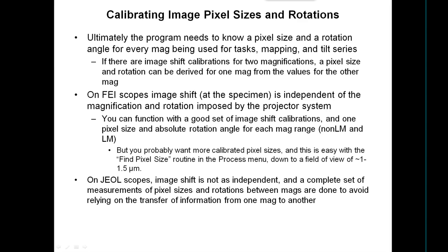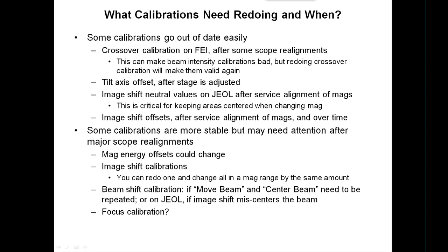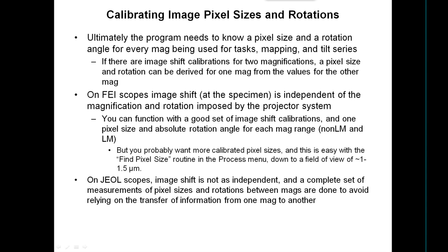With JEOL scopes — and the operator will go into detail on this — the image shift is not as independent of the magnification. What we've found is that we need a complete set of measurements of pixel sizes and rotations between the mags, to avoid having to rely on transferring information from one mag to another through the image shift calibrations.